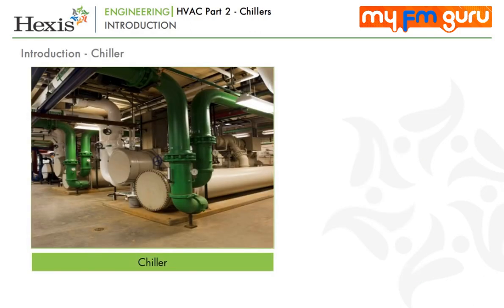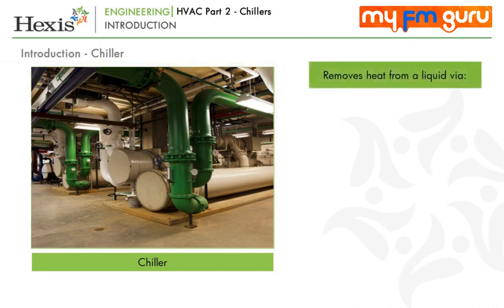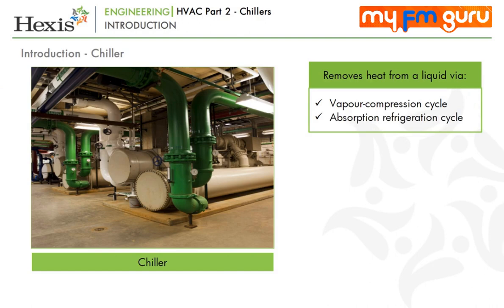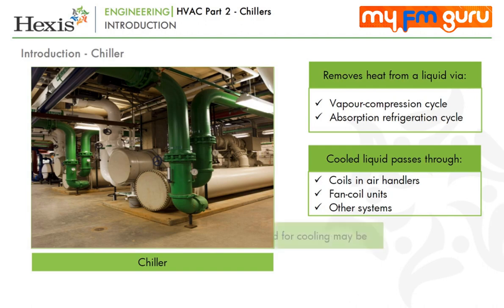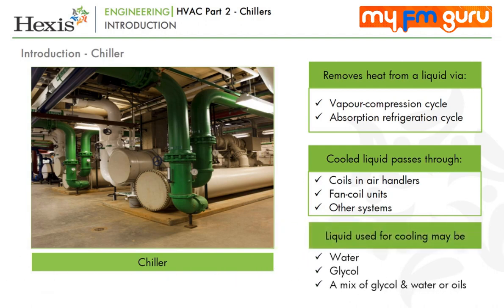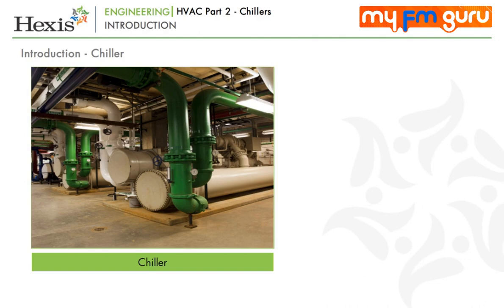A chiller can be described as a machine that removes heat from a liquid via a vapour compression or absorption refrigeration cycle to produce chilled liquid. This cooled liquid flows through pipes in a building and passes through coils in air handlers, fan coil units or other systems, cooling and usually dehumidifying the air in the building. The liquid used for cooling may be water, glycol, a mix of glycol and water, or oils. For general AC requirements, water is preferred due to lower cost, but some processes may require use of other liquids.